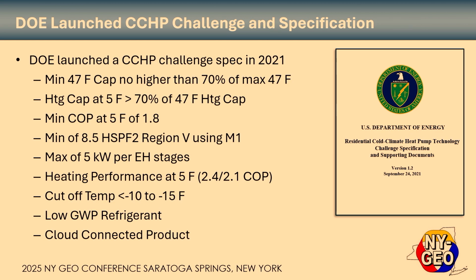Hence, the variable speed management is keeping track of what compressor speed it's running at based upon outdoor temperature. Minimum COP at 5 needed to be at least 1.8. Minimum of 8.5 HSPF2 for region 5 using the new M1 appendix. I'll go through most of the other stuff; you can probably read there. Essentially a low GWP refrigerant in 2021. Obviously, we were looking toward the new refrigerant, so they had to include all of that.